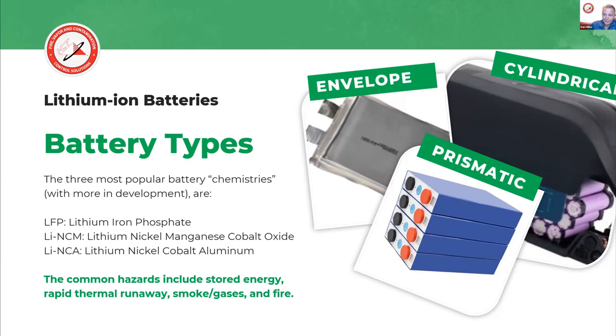There is one common denominator though, and that's the common hazards of all these batteries, at least the ones on the market so far: stored energy, which can shock you, and anytime there's stored energy, there's the ability to start a fire with it. Rapid thermal runaway, we'll talk about what that is and its definition shortly, but most of you have probably heard that term if you're on this webinar. And then there's smoke and gas emission from the batteries. The smoke is toxic, and the smoke and gas combination is also flammable and explosive. And then, of course, fire itself.